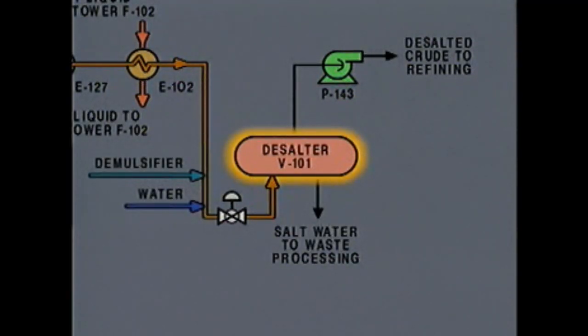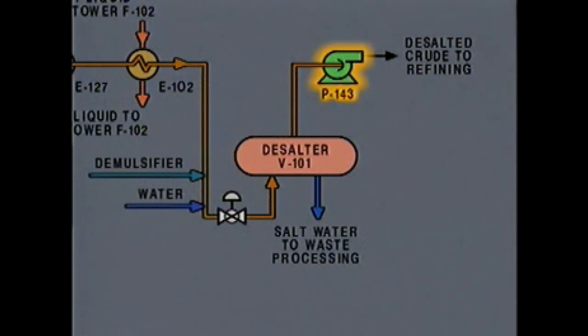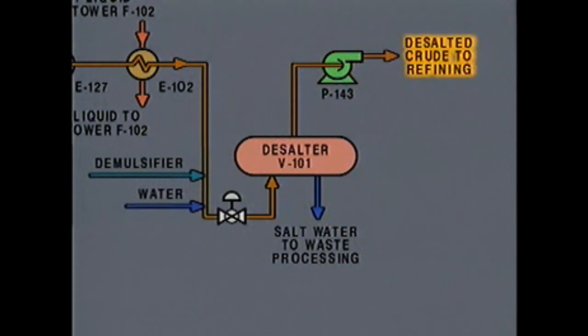In the desalter, water containing the salt and other impurities is drained from the bottom of the vessel and goes to a waste processing system. The oil is drawn off the top. Pump P-143 pumps the desalted crude from this system onto the next step in the process.